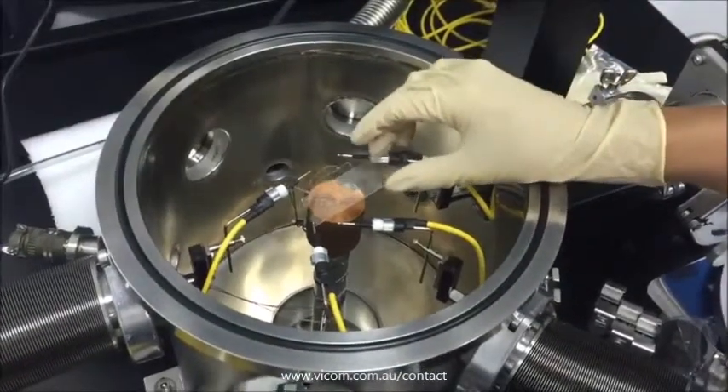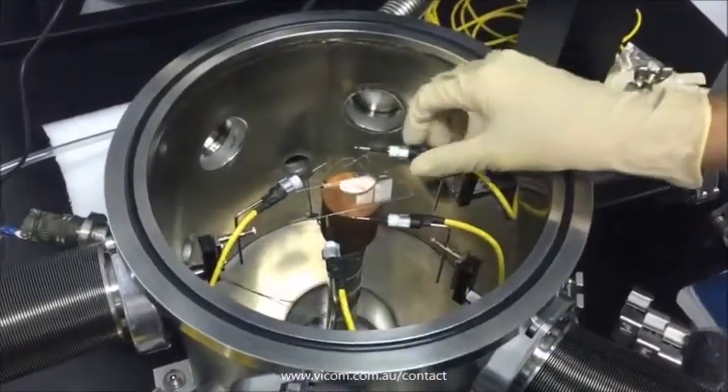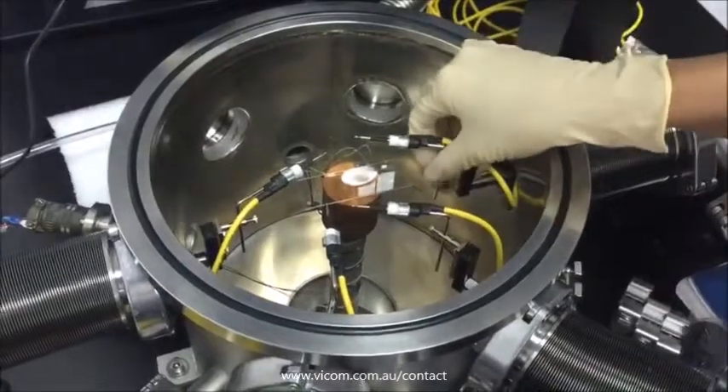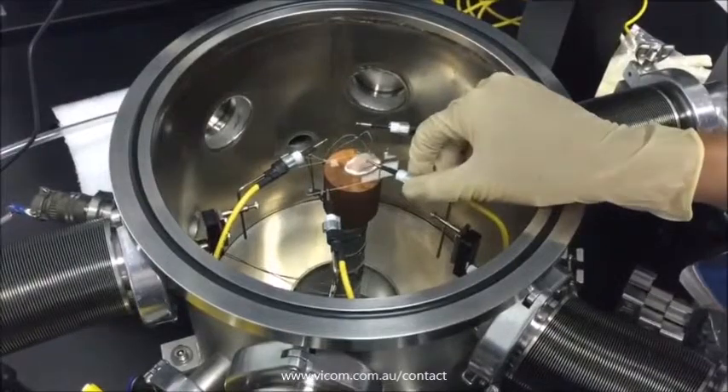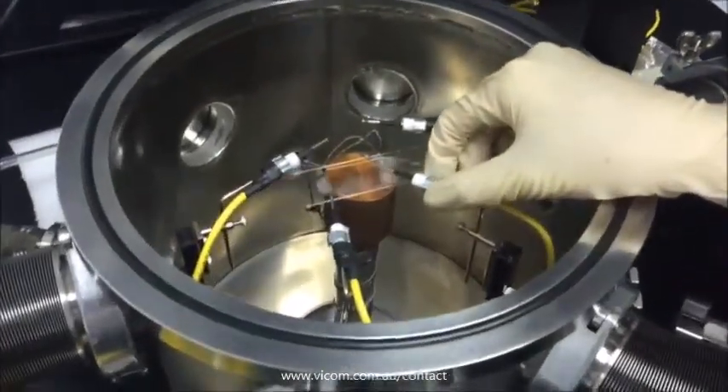The first step is to open the vacuum lid and use copper glue to fix the DUT on the chuck stage, and adjust the probe at an appropriate height to prevent the wafer from being heavily scraped by probes during pumping the chamber into the vacuum stage.